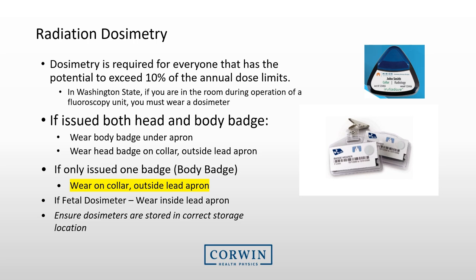If you are pregnant or have declared your pregnancy, you would be issued a dosimeter worn inside the lead apron. You also need to ensure dosimeters are stored in a correct storage location. Sometimes people leave their dosimeters on their lead aprons, and occasionally those lead aprons are left in the x-ray rooms, which can cause additional exposure on your dosimeter that you may not actually be receiving — resulting in an incorrect reading for you.